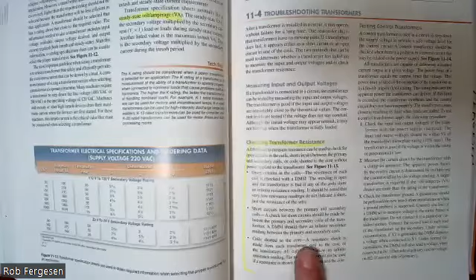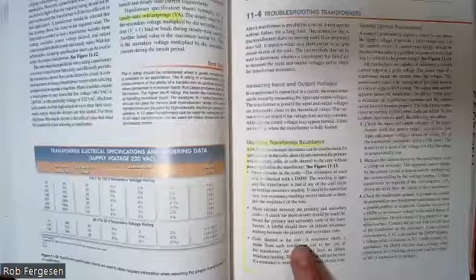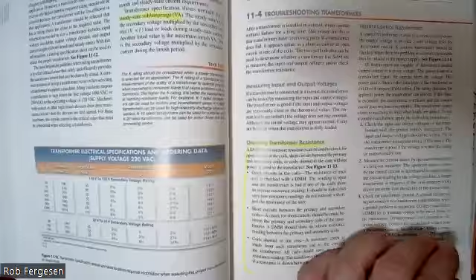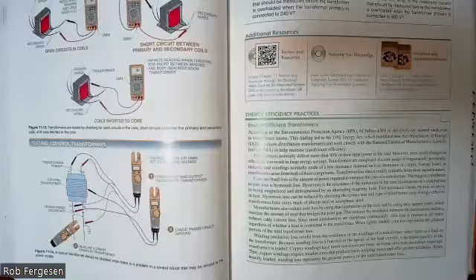And so you're looking for open circuits, you're looking for short circuits, and you also want to make sure that none of the coils are shorted to the core. In other words, something burned out on your insulation or got nicked because somebody bumped it, and now your coil is just up against a steel core. If it's doing that, then it could cause a problem as well. So the troubleshooting talks about some basic methods to do that, and I'm going to demonstrate that briefly tomorrow.